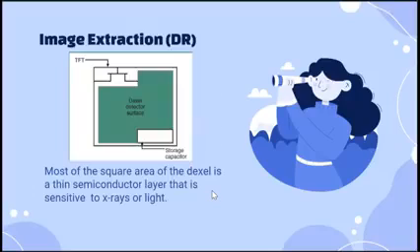Okay, so diba, as I have said in the prelim period, we have what we call a fill factor. Okay, so the more your Dexels get smaller, the fill factor decreases. Okay, when we say fill factor, it is this area here. So of course, if you're going to minimize the Dexel, the Dexel detector surface minimizes because the TFT and the storage capacitor do not decrease with it.